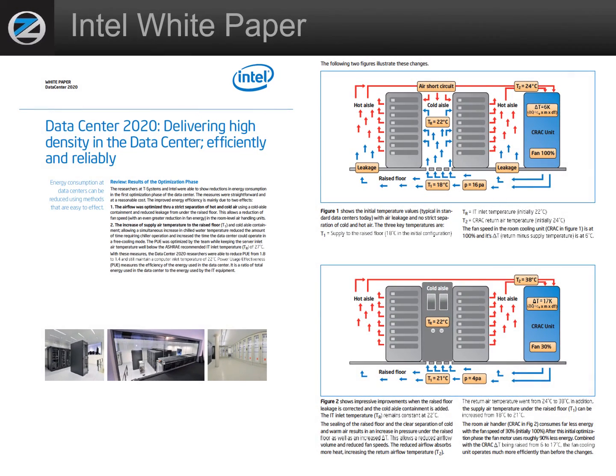This study, done by Intel, showed that strict separation of cold and hot air and increasing the set point because of the more efficient structure of airflow was the two main benefits of containment. In the test example shown here, it dropped the PUE from 1.8 to 1.4, which is considerable.